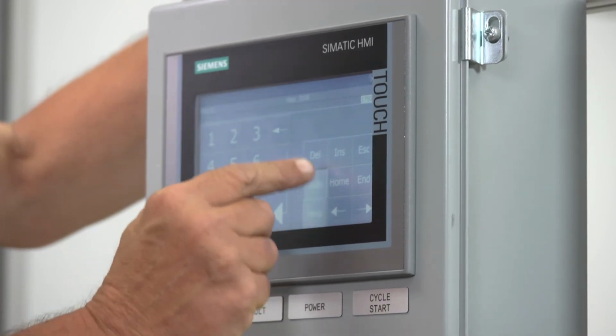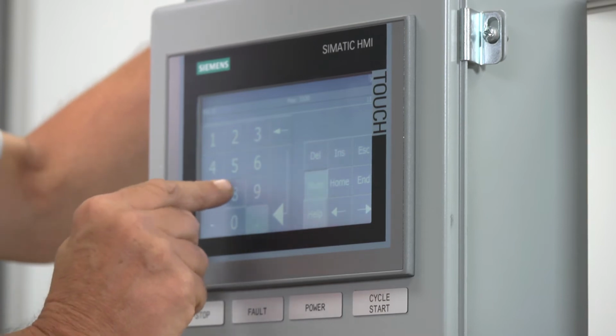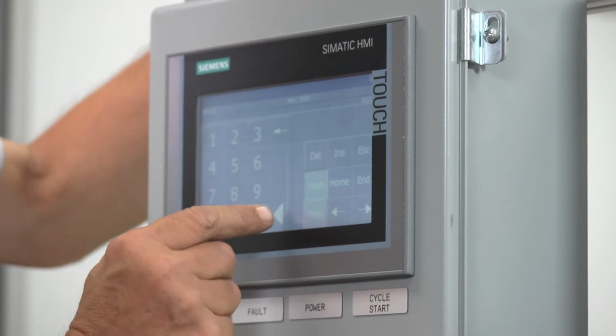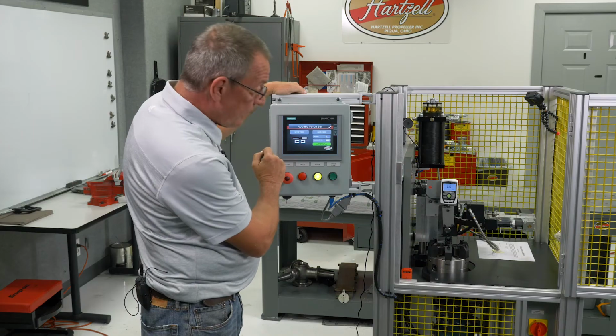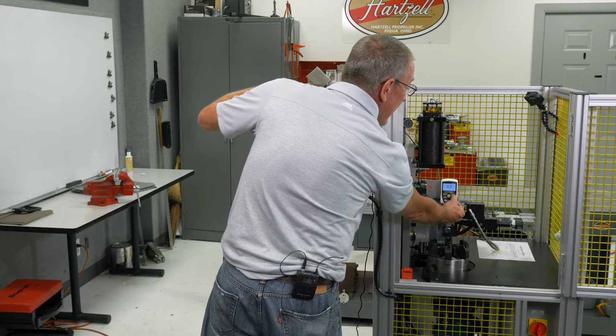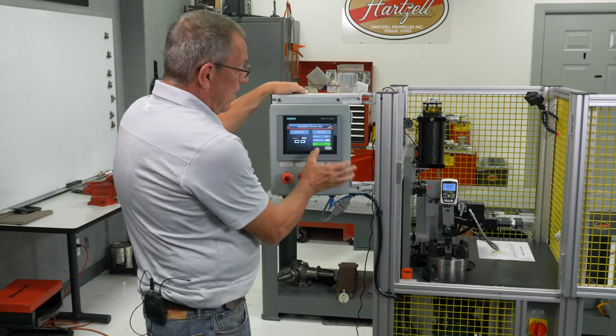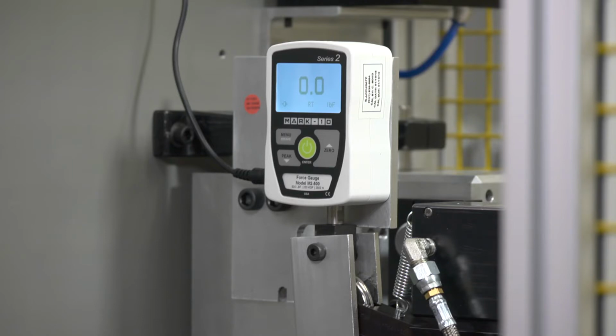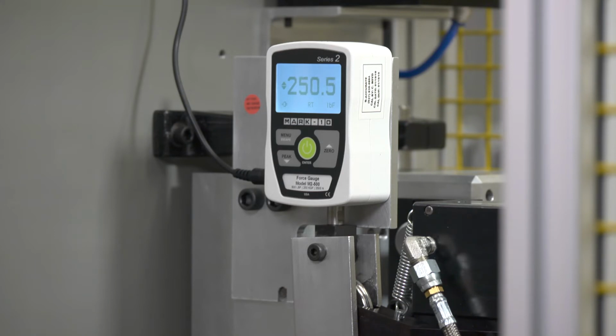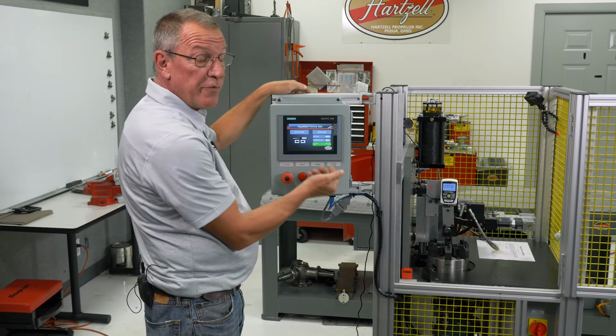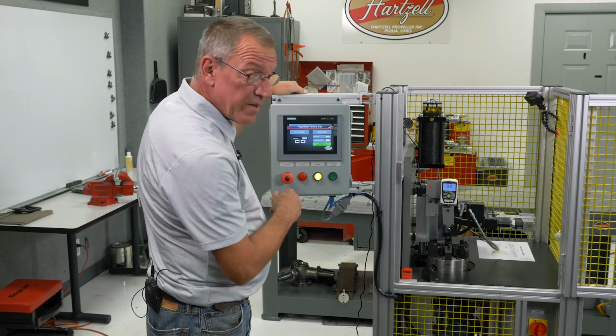And that gives me 1,822. So I'll reset the set PSI to 1,822 and hit enter. Once again, I'll zero my gauge, press and hold. And I'm showing 251. I'm looking for 250 plus or minus 2, so I'm within tolerance.